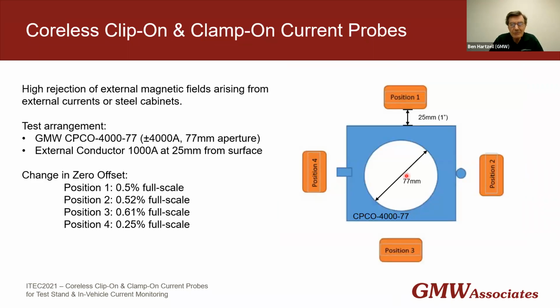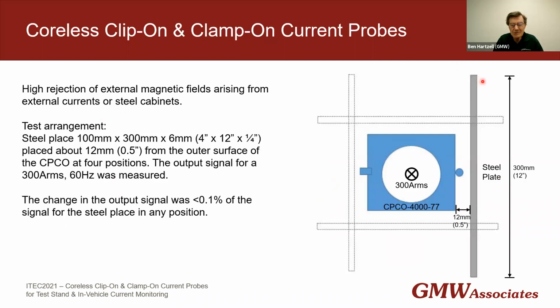Now, to show that external fields do not interfere with the probe, this is a 77 millimeter probe. And around the outside, we're putting high currents, about 1,000 amps at each of these positions. And it's a 4,000 amp probe. And the zero offset when these high currents are placed near the outside of the sensor is in each case less than about 0.5%. We can try a similar thing with a steel plate. This is what you might expect if you have one of these current probes in a cabinet. This is a 12-inch 300 millimeter plate, and it's put in each of 4 positions. And as we change these plates around the CPCO, the change in the 300 amp RMS signal is less than 0.1%.